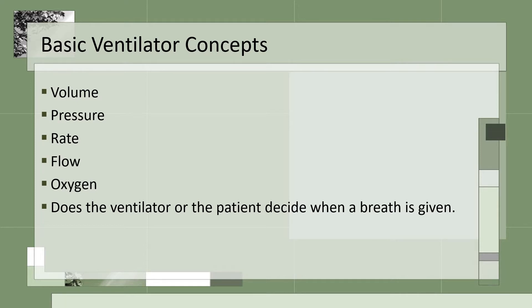The basic ventilator concepts are: volume — the amount of air going in and out; pressure — the amount of pressure used for inhalation and exhalation; rate — the number of breaths; flow — time allowed for air going in; oxygen — the amount of supplemental oxygen needed, also called FiO2. The sixth concept is deciding whether the patient takes a breath or the ventilator takes a breath. The combination of all these concepts provides different ventilator modes.